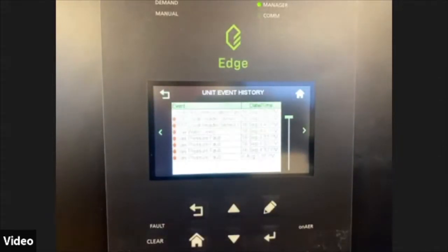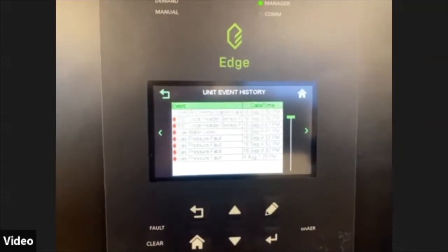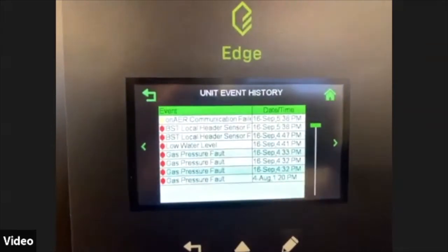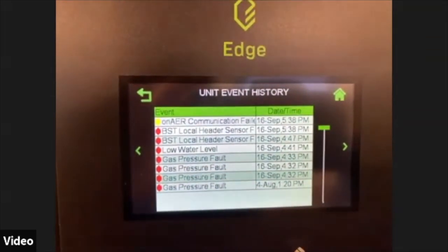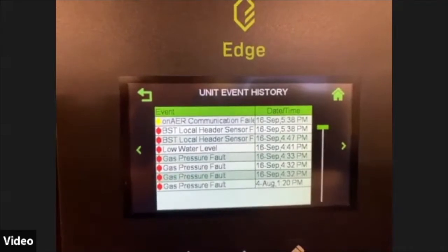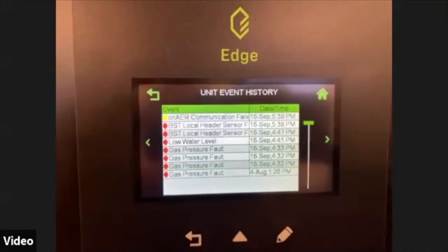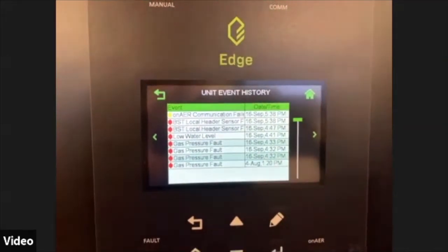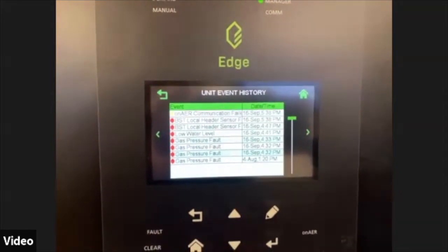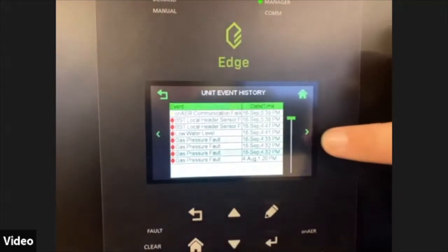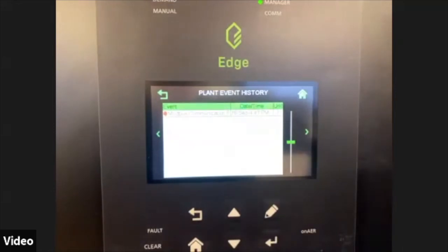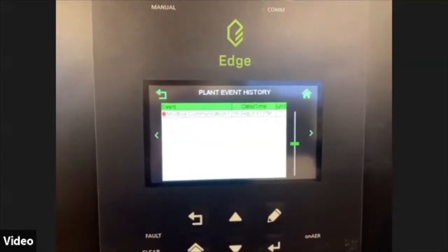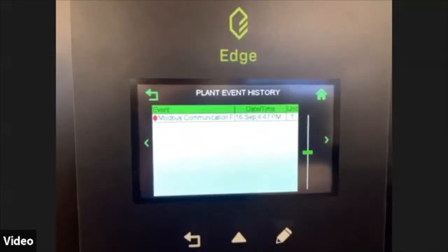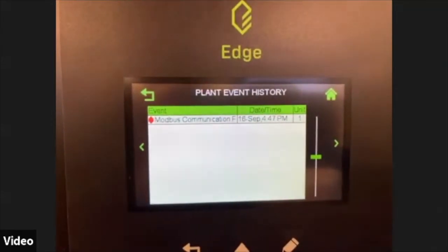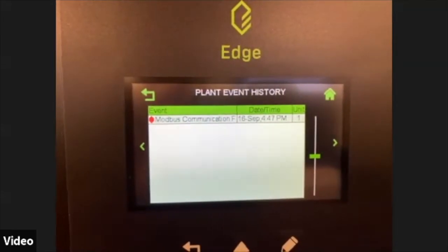The next screen is the unit event history. This is the alarm log just for this boiler. So if you get into this screen, you can see the time and date and what fault happened just for this boiler. That'll help you troubleshoot many things. And since this boiler is the manager, it also gives you a plant event history. So what this one will do is you'll see the alarms from all 16 boilers on this screen.